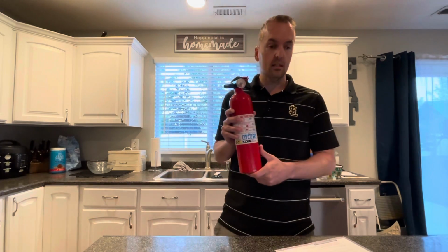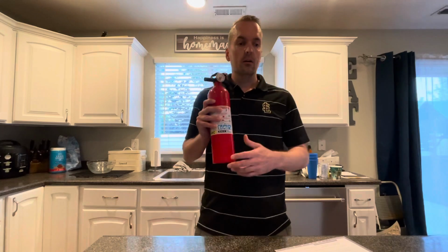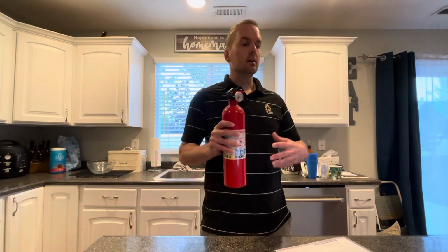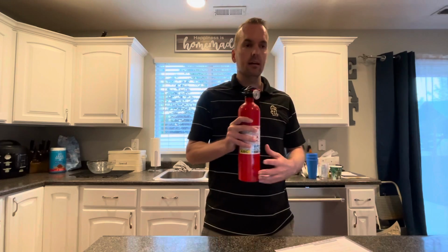Portable extinguisher placement, as it refers to a business, would be you want to place it in normal paths of travel, where everybody's traveling generally towards an exit is where they're going to be going if there is a fire. So if there's one near an exit, it's going to be to their advantage. Also in visible locations. And if it's not obvious, then we need to have signage, we need to have lights, etc. to point people to that extinguisher.